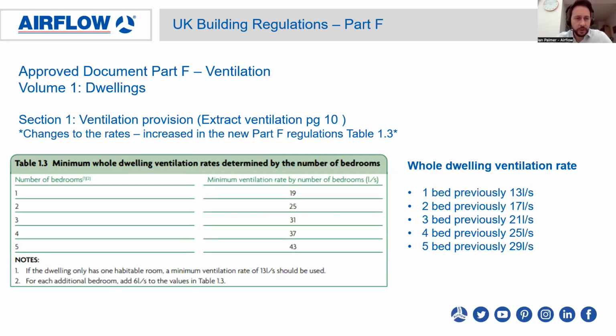Table 1.3, this shows the minimum whole dwelling ventilation rate determined by the number of bedrooms. So to the right of this slide, you can see what the previous rates were. For example, for a 1 bed the minimum rate used to be 13 litres a second, it's now 19. And you'll see each one is increased, even going up to the 5-bed property. The minimum ventilation rate used to be 29 litres a second, it's now 43. So these are quite significant changes because this will increase the size of your ventilation unit and your ventilation system.